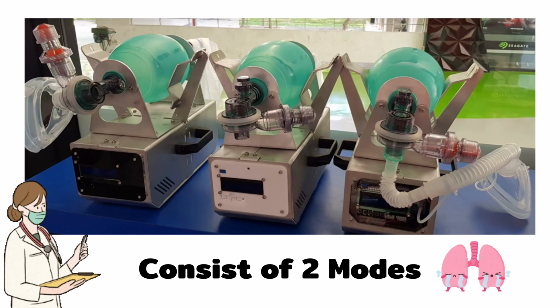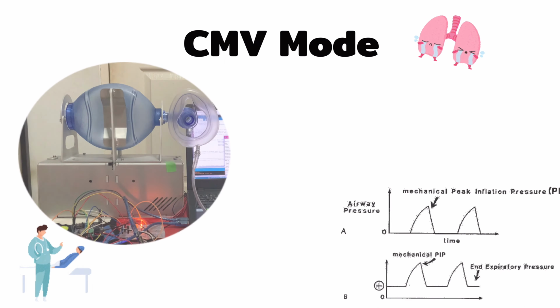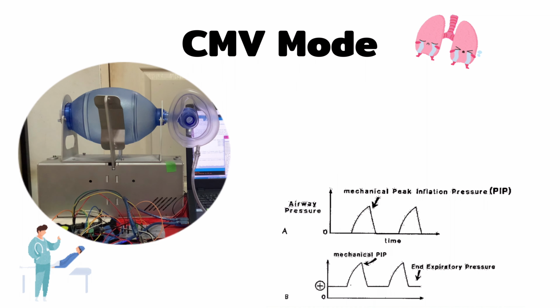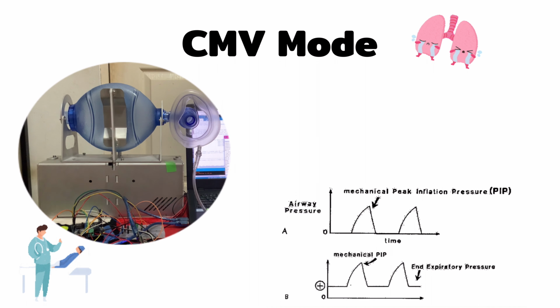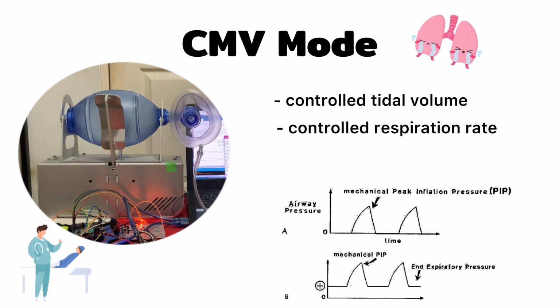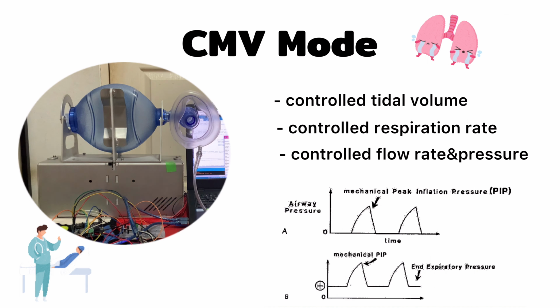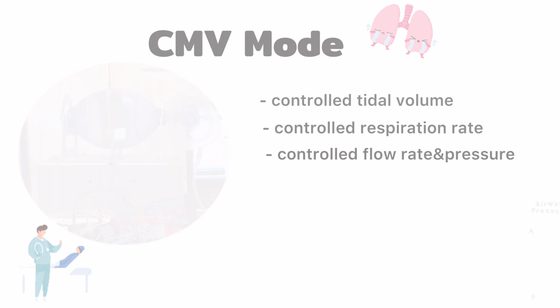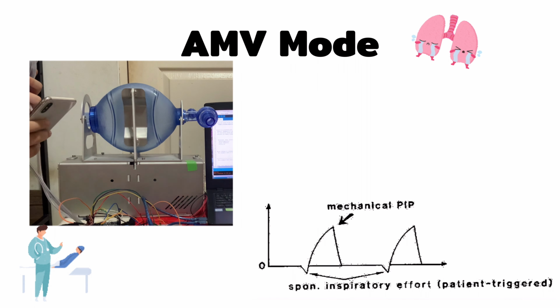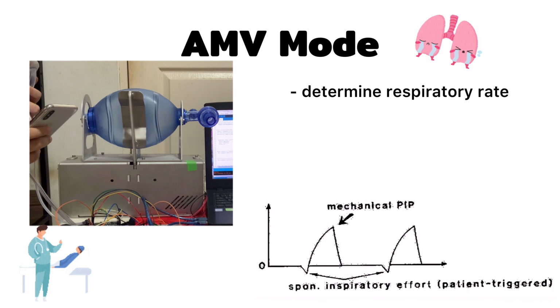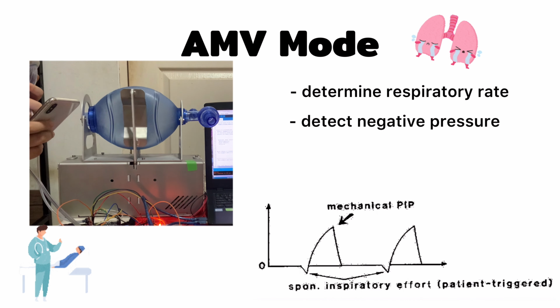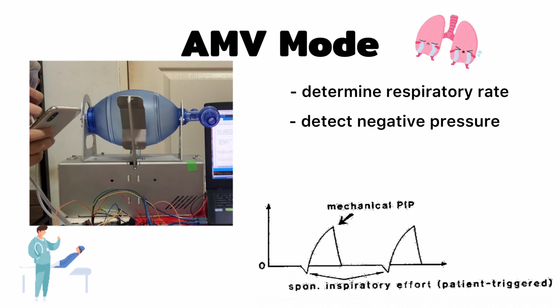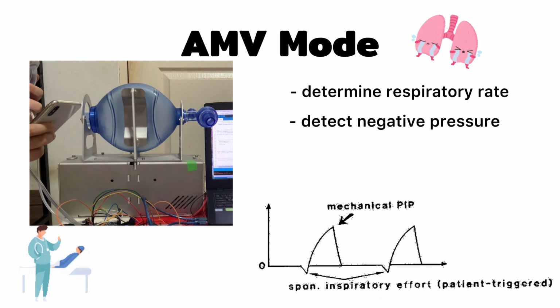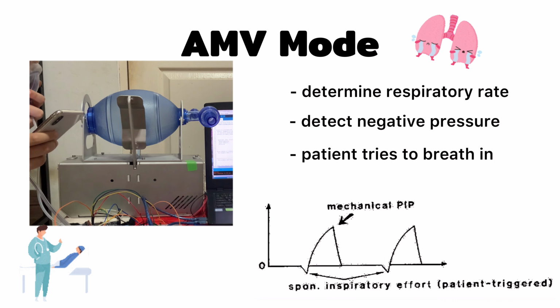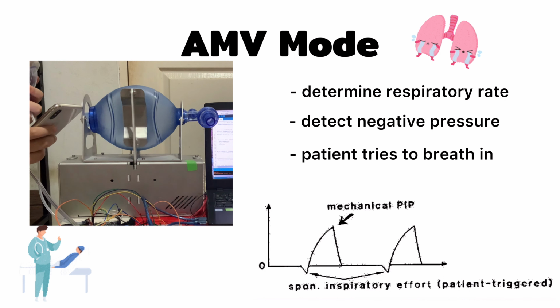Our emergency ventilator has two modes. The first is CMV, or continuous mandatory ventilation, the mode in which all parameters, including tidal volume, respiration rate, flow rate, and pressure, are totally controlled by the ventilator. This is used with patients who have lost consciousness. The second is AMV, or assist mode, in which the patient determines the respiration rate. The onset of the inspiratory phase is detected by measuring negative pressure, indicating that the patient is trying to breathe in, but the other ventilation parameters are set by the ventilator.